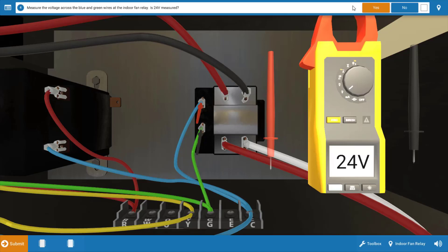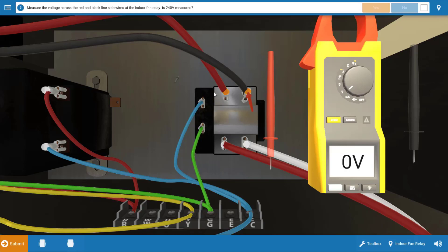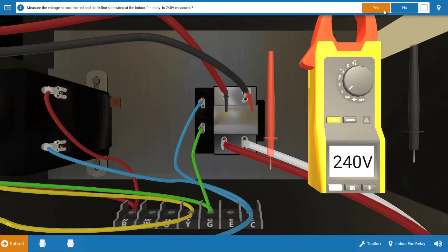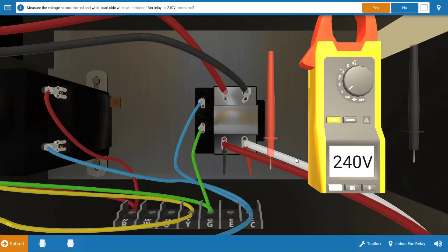Our next step is to measure for line voltage to the relay. The relay has 240 volts coming in on the line side. And when the contacts close, we should get 240 volts out of the load side to the motor and capacitor. Now that we've verified we've got 240 volts coming into the relay, we're going to check the load side voltage of the relay and verify that the relay is in fact functioning. Place your meter leads on the glowing orange hotspots and we do have load side voltage of 240 volts. This eliminates the indoor fan relay as a possible cause.